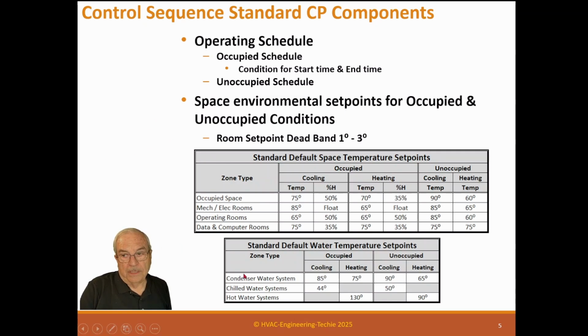So for condenser water systems, which we'll be dealing with in this session, cooling is 85 and heating is 75. Now, the one good thing about these is water-cooled equipment is really forgiving about temperature. It has a wide band. Many systems have a very close band, maybe a 10-degree band or a 20-degree band. Well, in condenser water, we can be a lot bigger.